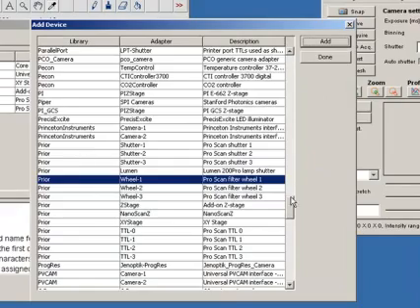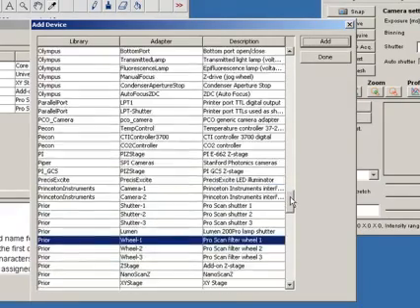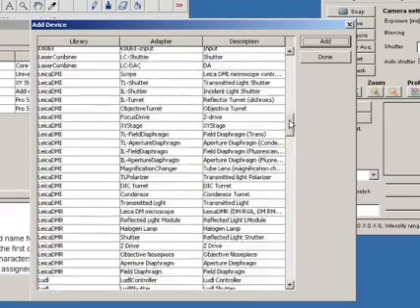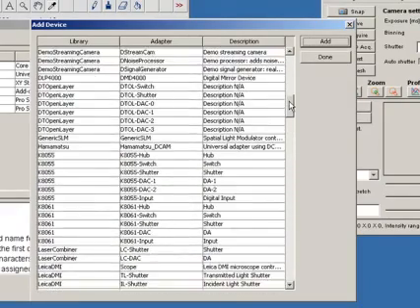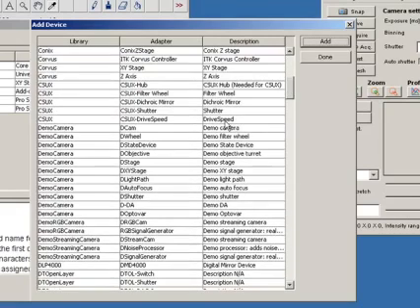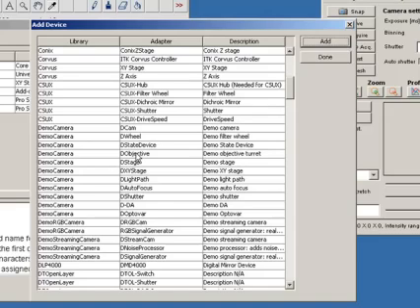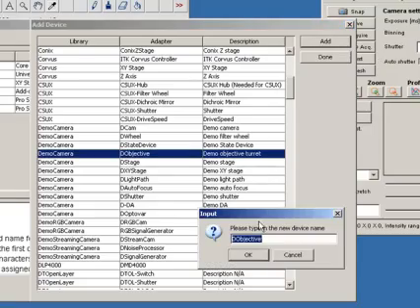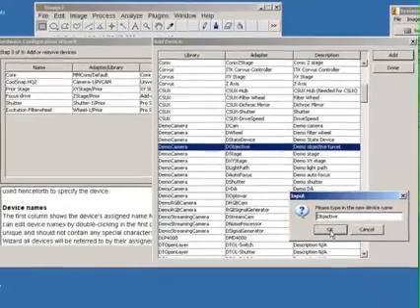And then, the final thing which is worth always adding is you've also got on the list here a whole host of dummy drivers. And it's worth adding in the dummy objective here because I've not got a motorized microscope. I'm actually using Olympus BX51. But it's worthwhile adding in the dummy objectives because that means we can set objectives and create calibration files and all that sort of thing as well. So, let's add that one in there and just call it objective.